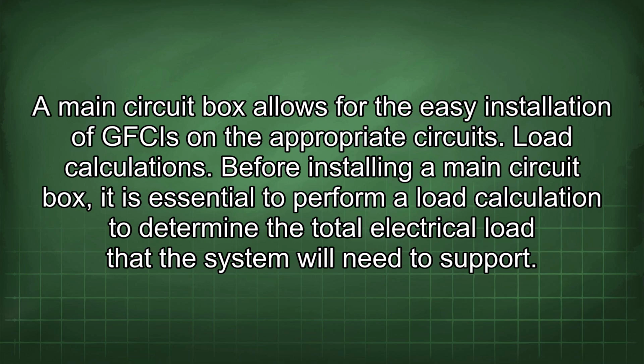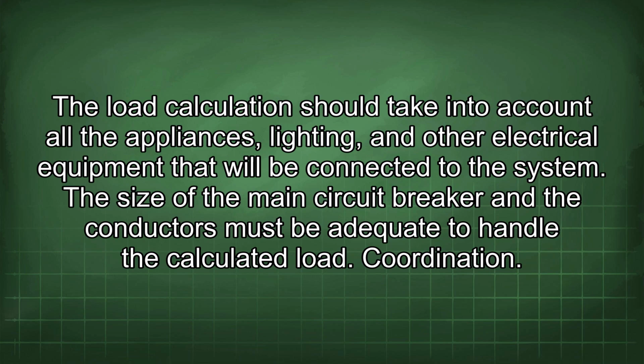Load calculations. Before installing a main circuit box, it is essential to perform a load calculation to determine the total electrical load that the system will need to support. The load calculation should take into account all the appliances, lighting, and other electrical equipment that will be connected to the system. The size of the main circuit breaker and the conductors must be adequate to handle the calculated load.